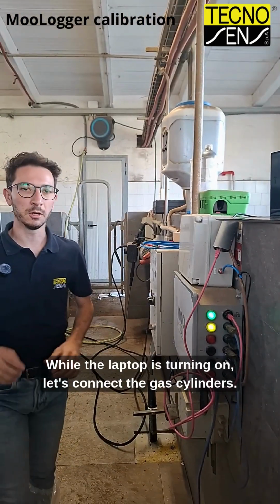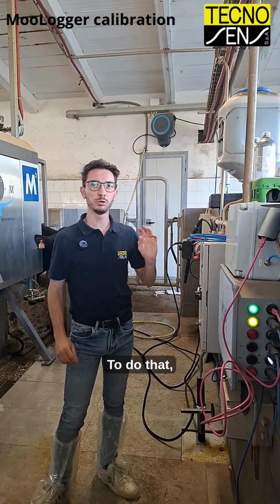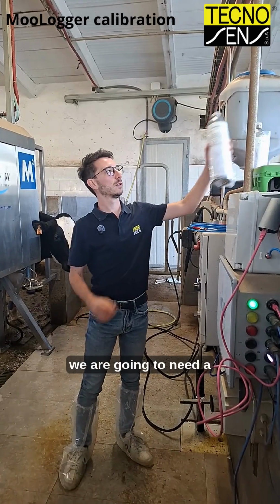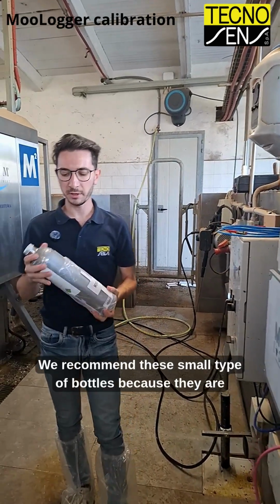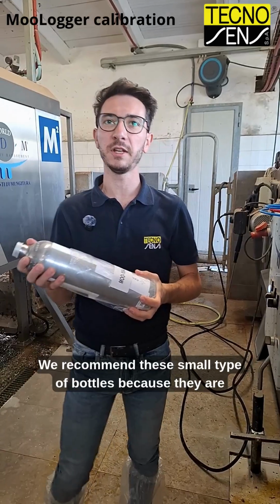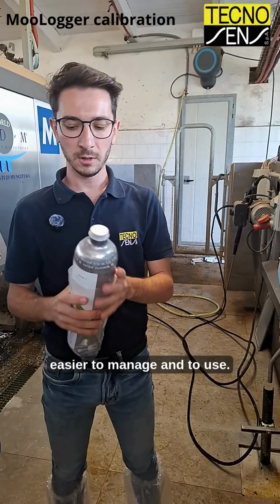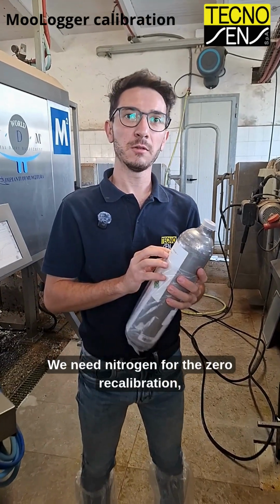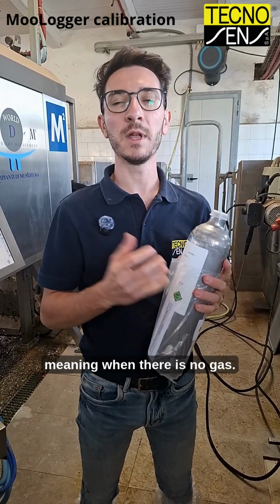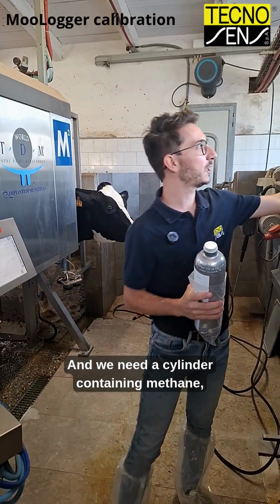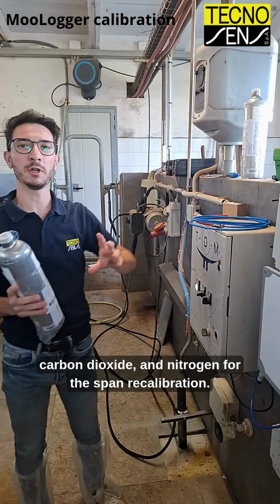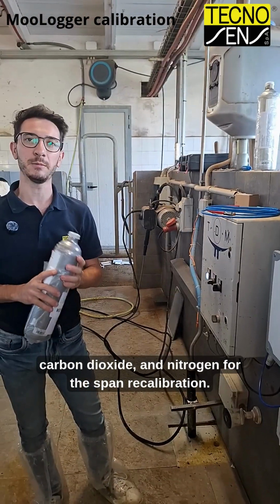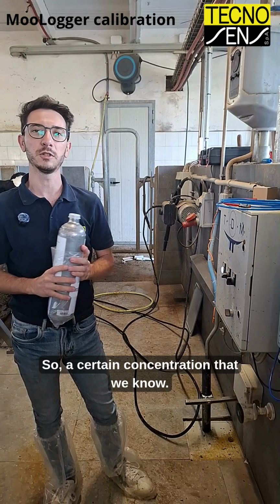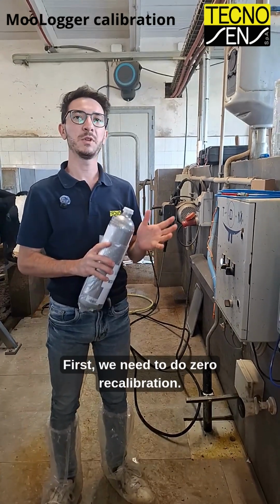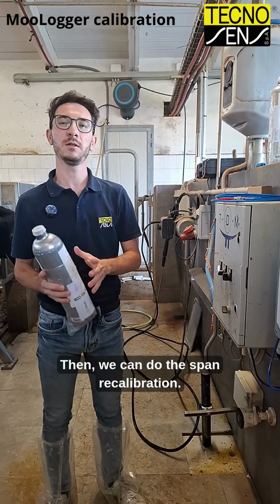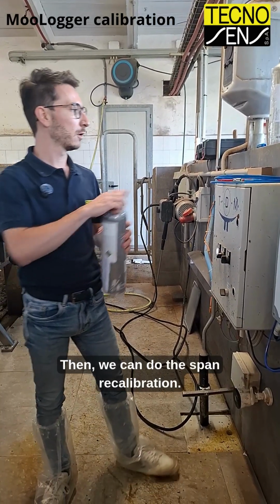While the laptop is turning on, let's connect the gas cylinders. To do that, we are going to need a gas cylinder. We recommend this small type of bottles because they are easier to manage and to use. We need nitrogen for the zero recalibration, meaning when there is no gas. And we need a cylinder containing methane, carbon dioxide, and nitrogen for the span recalibration. So a certain concentration that we know. First, we need to do zero recalibration, then we can do the span recalibration.